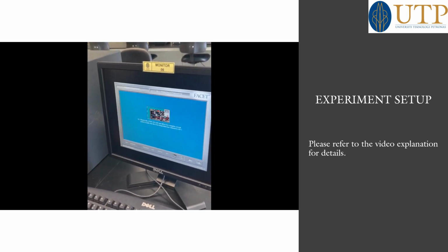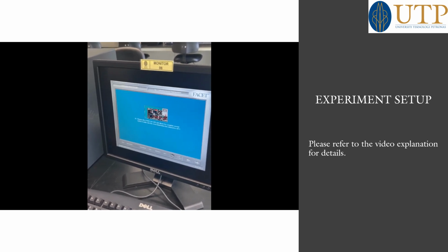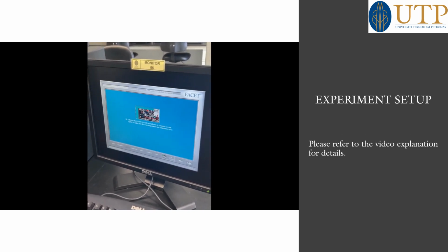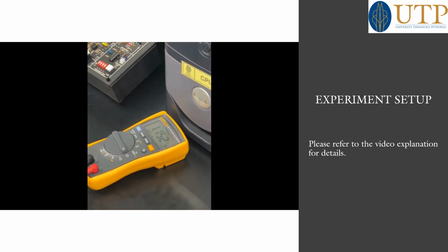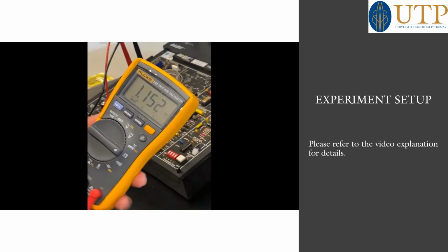Observe the oven ON LED and allow it to complete several cycles. Make sure the temperature has returned to 40. Record the RTD resistance at 40 degrees. When you record this on the RTD circuit, you will get this result: 1158 ohm. You will calculate.